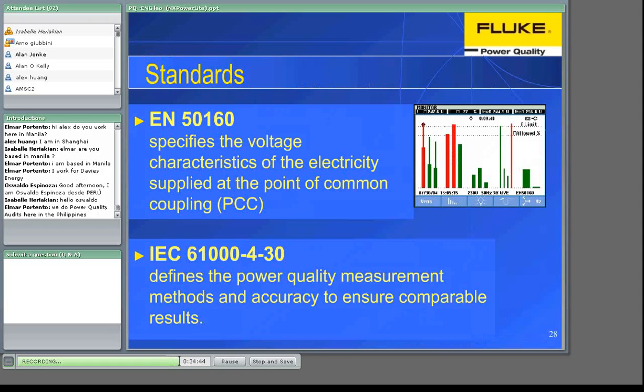We now approach the end, and we will see the two main standards used in this field about power quality analysis. The first one is the 50160, which specifies the limit values of voltage characteristic at the point of common coupling, PCC, and it is applied at the low and medium voltage level.